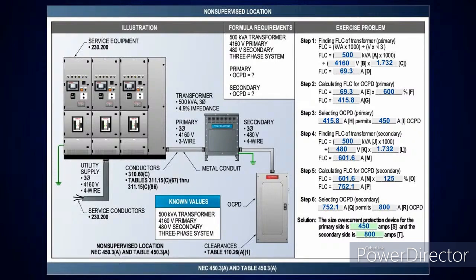Right. All right. Now, this is non-supervised, okay? So when you look at table 450.3(A), you're going to see your location limitations there, and you're just going to use any location here, okay? So it's other than supervised, okay? It's non-supervised. Now, when I look at this problem here, I'm going to do the primary and secondary, and I'm going to look at the illustration. I'm going to pull out the most important information. I've got a 500 kVA transformer. Now, one of the interesting parts here is I want to point out it has a 4.9% impedance. So when you're looking at that table, the second column is going to be your transformer rated impedance, and I'm not going to be more than 6%. So that's the column going across I'm going to use.